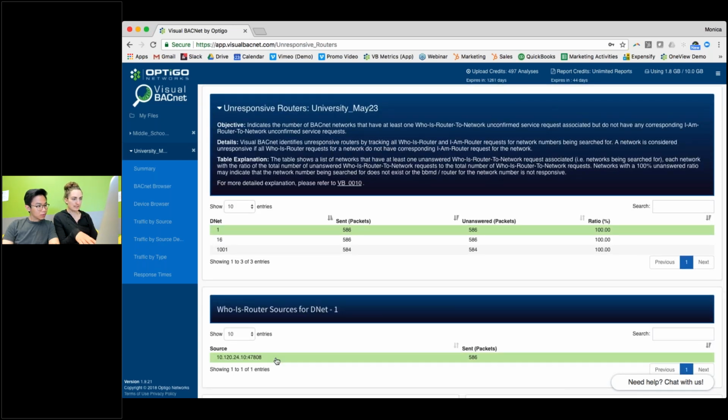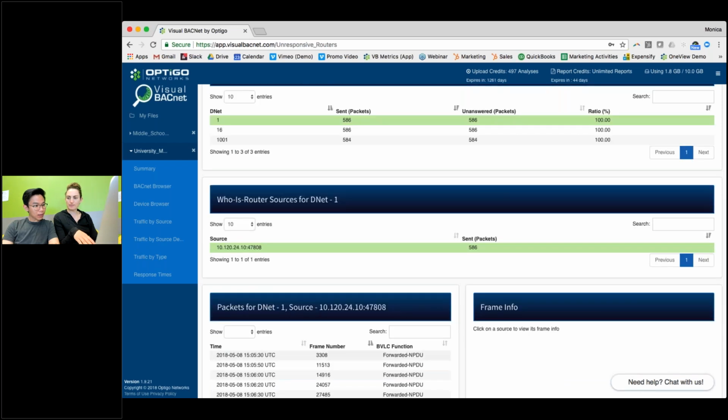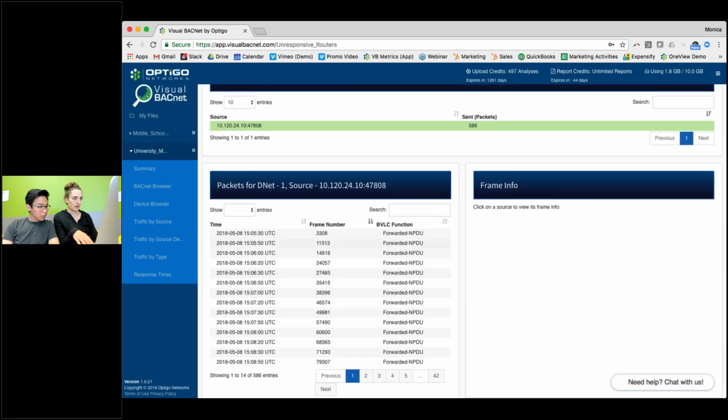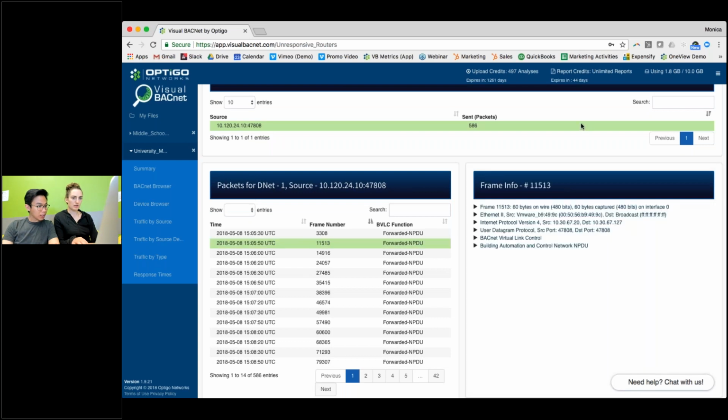Okay, that looks like, is that the same? Okay. These are all on BBMD. Oh, they're all forwarded. It's looking for it every 20 seconds and then 10 seconds, 20 seconds, 10 seconds. Oh, that's a fun pattern. Yeah. So 0, 20, 30, 50, 0, 20, 30, 50.